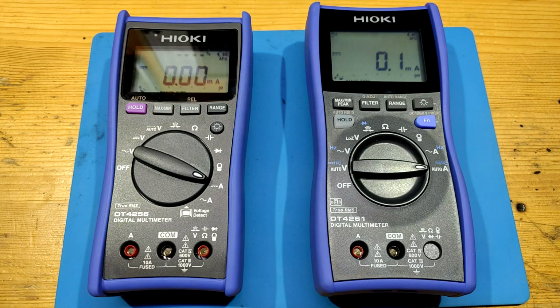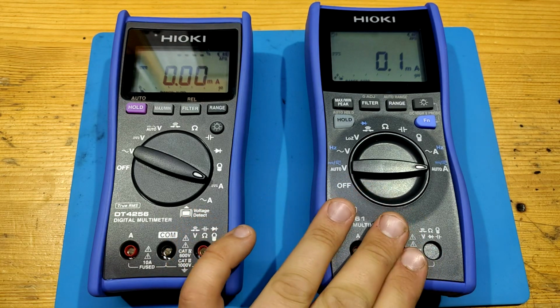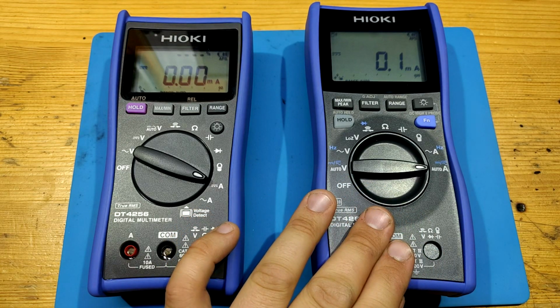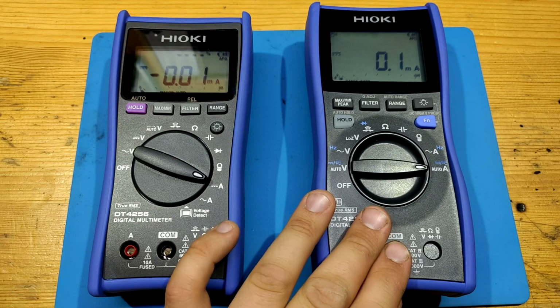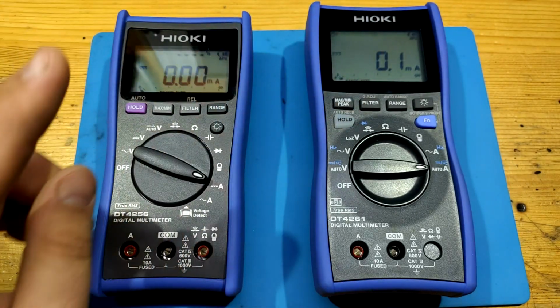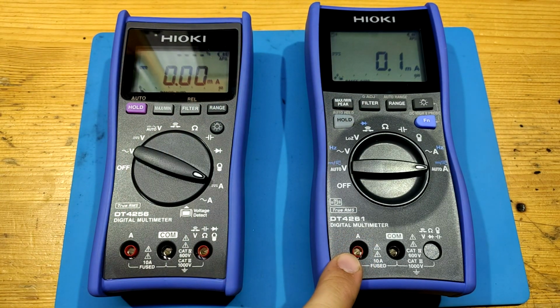0.38 is overall acceptable for generic measurement, as the borderline is somewhere around 0.5%, but being on range that doesn't cover all digits, it roughly covers 2 digits, it's always limiting your reading to increasing error from value. And that's the practical difference between error from range and error from value. While error from range may be just 0.38% and it's acceptable, the error from value is huge because you only use half of the display, and that's about the only higher currents being there.